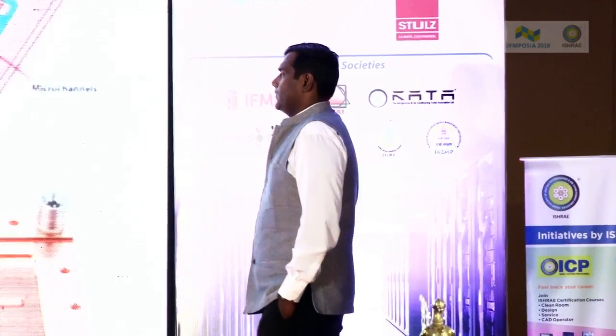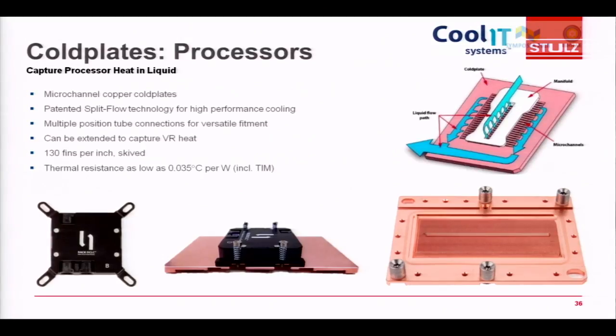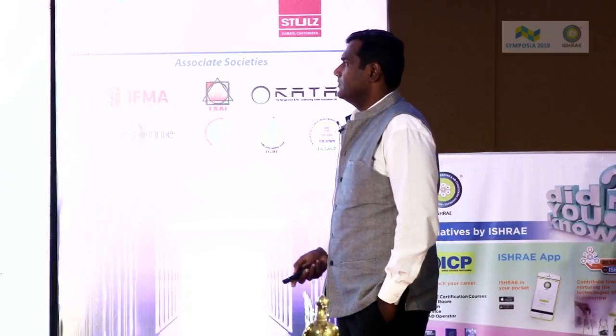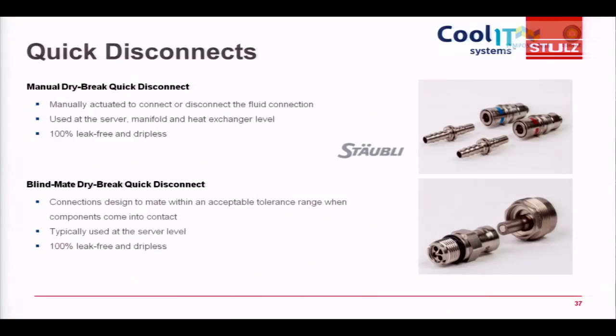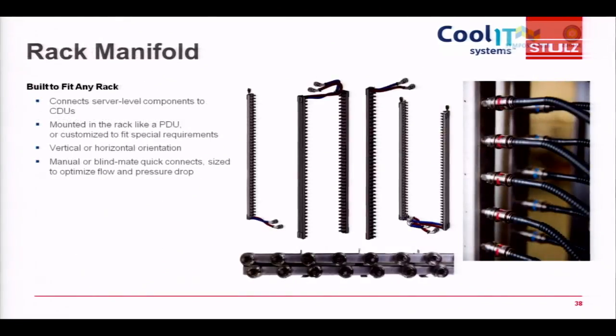This is a typical plate-to-plate heat exchanger, which is used in air conditioning or in heat transfer in industrial cooling businesses. It's ultimately the same thing. Of course, it's a different kind of design. It's more efficient. And this is the core which will take out the heat. Quick connections have improved over a period of time to make sure that there is no dripping and no water moving into the servers, to secure the equipment. Manifolds are pretty similar again to a piping design which we do on a large scale for a big building. It's absolutely similar to that.